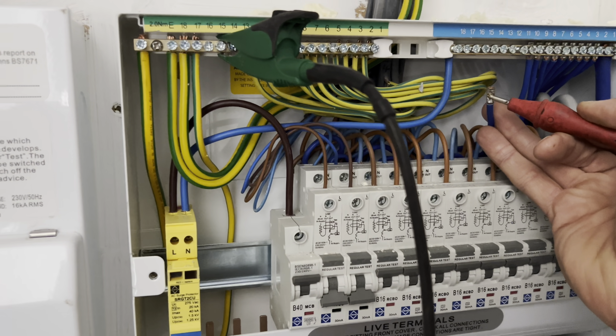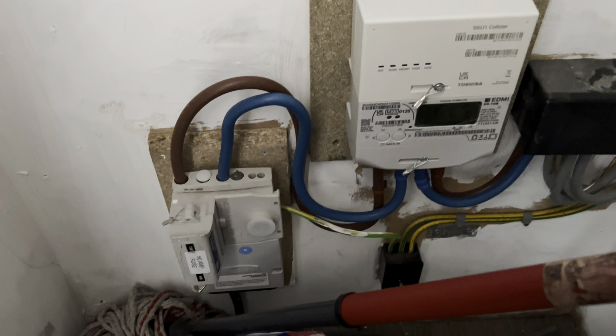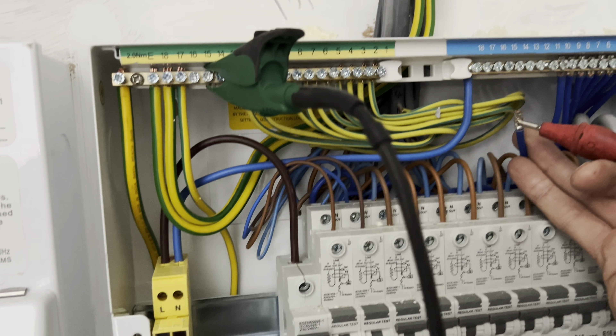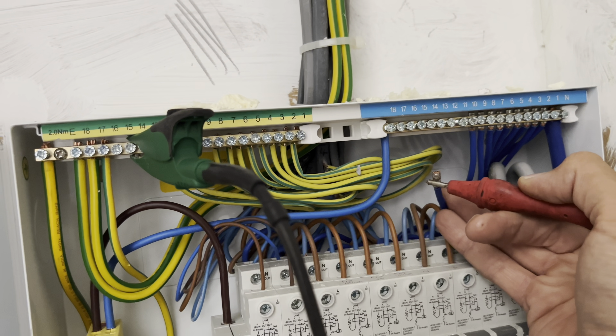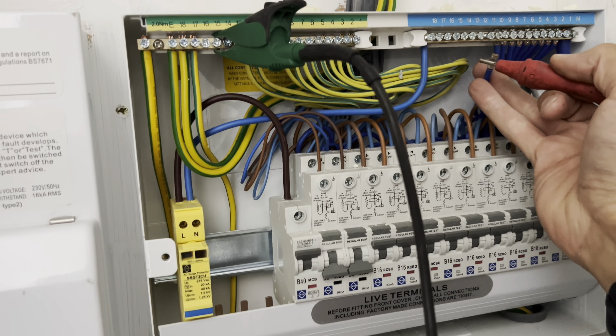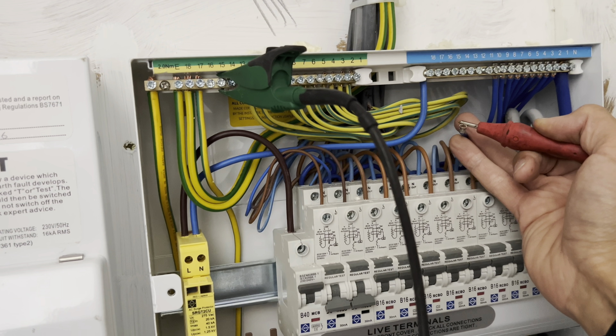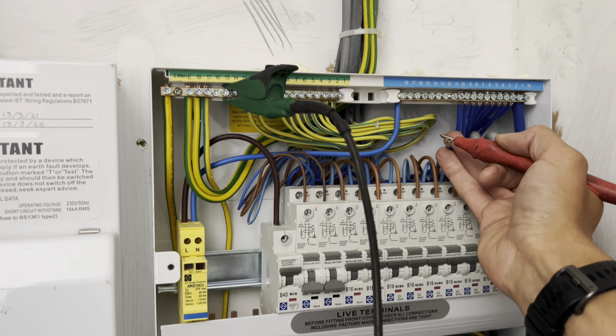So I'll put my tester on here. I'm going between earth and neutral, where I shouldn't have anything — because technically on this PME system they're the same. I'm checking the neutral of the lighting circuit, not the neutral going back to the mains. I'm going to do it on the neutral of the actual RCBO to see if I might be getting some voltage tracking back through somewhere. I get 3.6 volts. It's very modest — not really what I'd expect to see if it's causing lights to fire up. I'd be expecting around 50 volts or something like that.